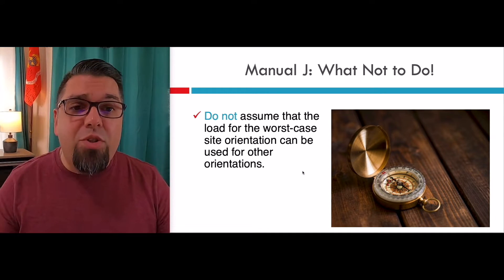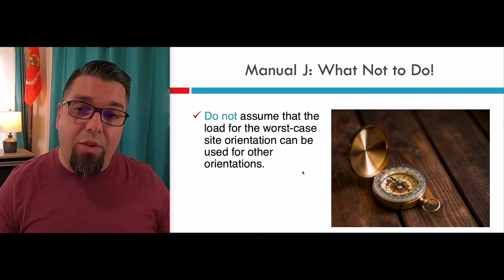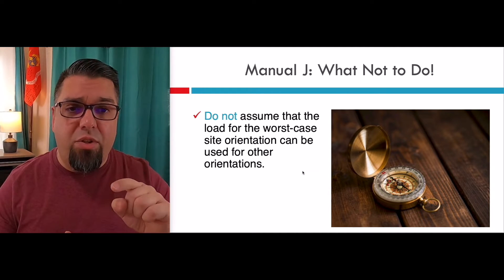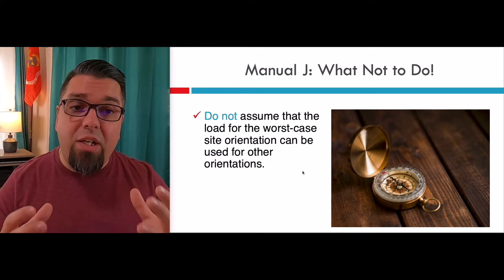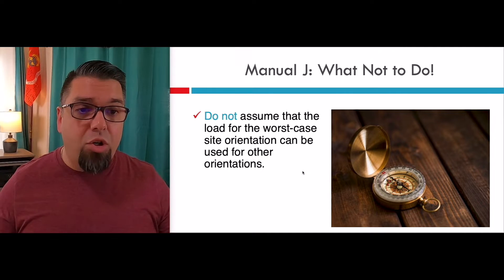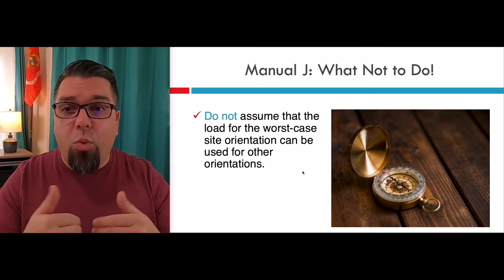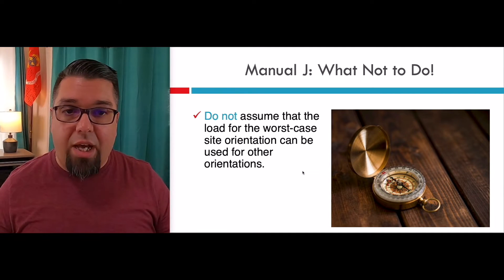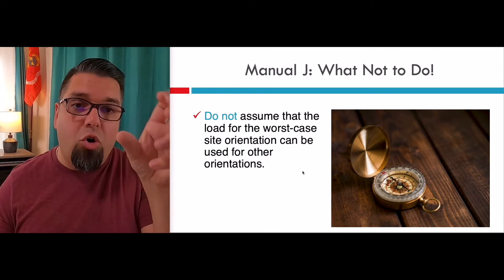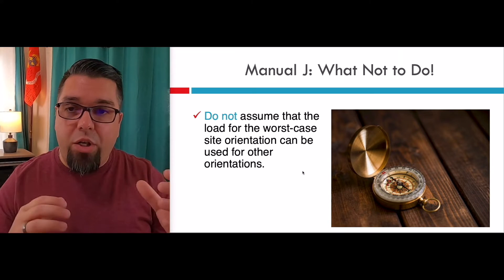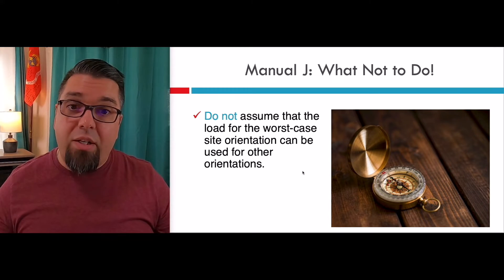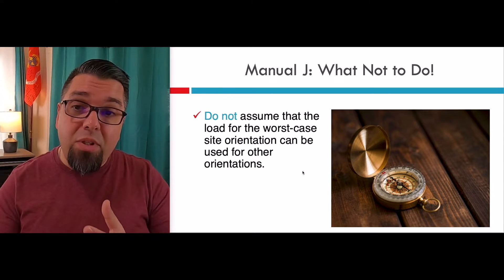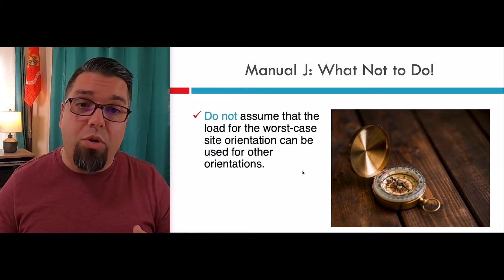Don't assume the load for the worst-case site orientation can be used for all homes. Put in the actual direction of north. If you didn't capture that on the site survey, just Google the address — Google Maps will show you the home's orientation, and you know where the front door is. If you're doing new construction on a cul-de-sac, the load will be different as you move the same style home around it, because windows and shading face different directions and the cooling gain changes. Heat loss would probably be the same, but cooling gain impacts the size of your air conditioner and possibly the furnace blower.